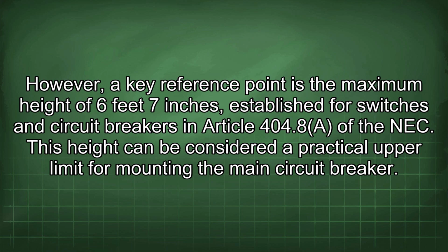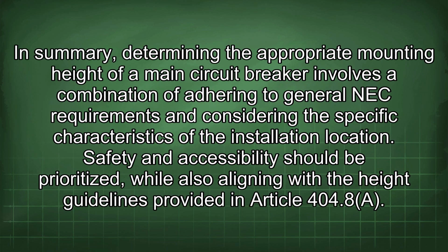However, a key reference point is the maximum height of 6 feet 7 inches, established for switches and circuit breakers in Article 404.8(A) of the NEC. This height can be considered a practical upper limit for mounting the main circuit breaker. In summary, determining the appropriate mounting height of a main circuit breaker involves a combination of adhering to general NEC requirements and considering the specific characteristics of the installation location. Safety and accessibility should be prioritized, while also aligning with the height guidelines provided in Article 404.8a.